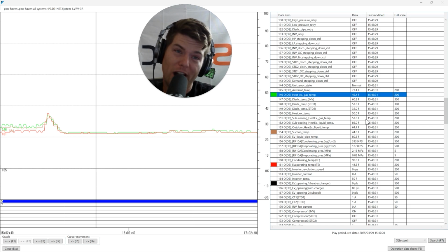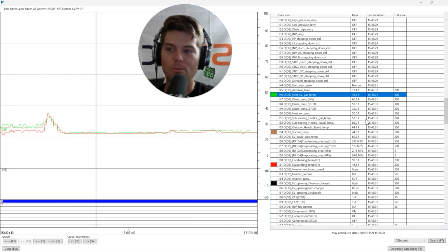And guess what happens? When I shut that liquid line, whoa, my discharge superheat goes up. Whoa, my suction superheat goes up. Whoa, everything looks amazing. There we go. Perfect, right? And this can be done on site. Go up to the unit, close that liquid line, right? You've locked that unit out, leave the suction line open, and you're done.